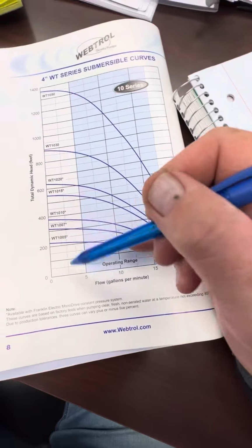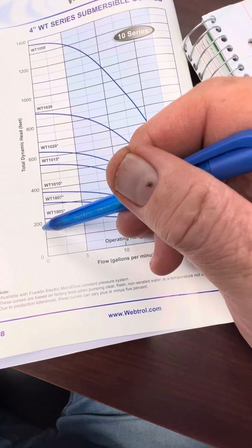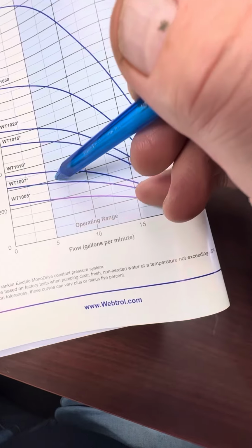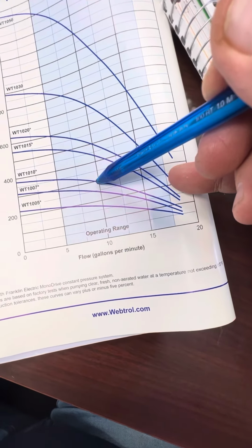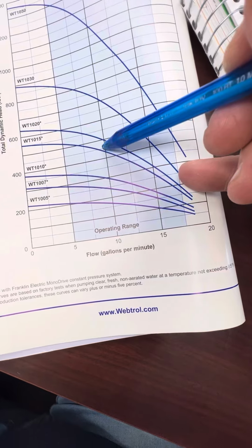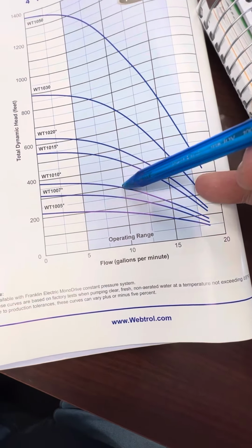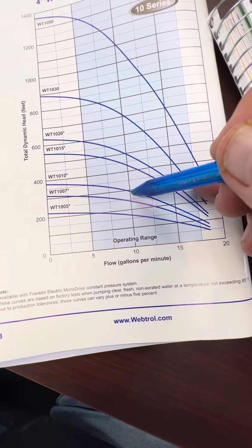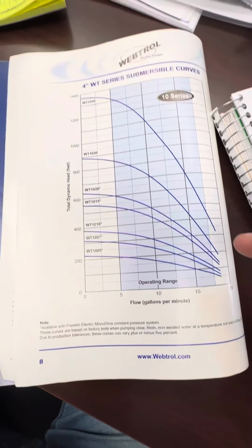Different brand pump, same idea. So 180-foot pumping level, add 115 more, so it's going to put you right there close to 300. You're going to scroll across. There's your 10 gallons a minute. Your one horse is just a little bit under it. Your one and a half horse exceeds it. So you would pick the one and a half horse if possible. If they're on a budget or they're already set up with a one horse, then you could probably squeak by with one horse. That's how to read a pump curve.